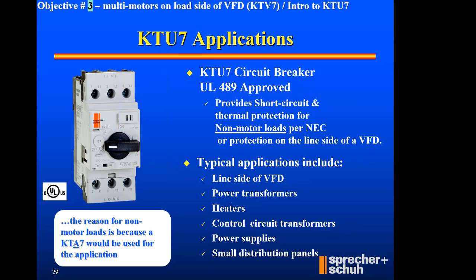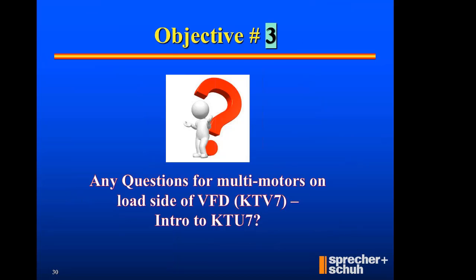Okay, what does KTU give us? The typical applications: line side of a VFD, protection for power transformers. Okay, we said non-motor loads. Well, a heater is a non-motor load, so certainly UL 489 protection on the line side can comply. So that's an application. Protection for the control circuit transformers, protection for power supplies, small distribution panels. So just letting you know that, hey, we've got a UL 489 approved circuit breaker device.